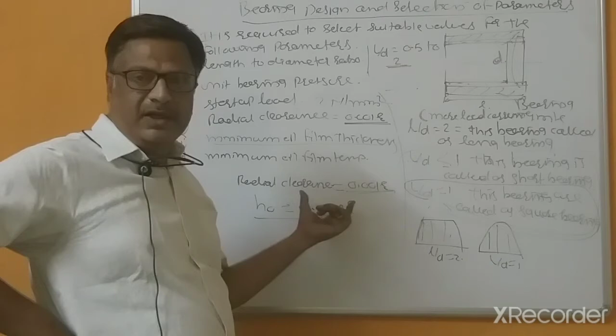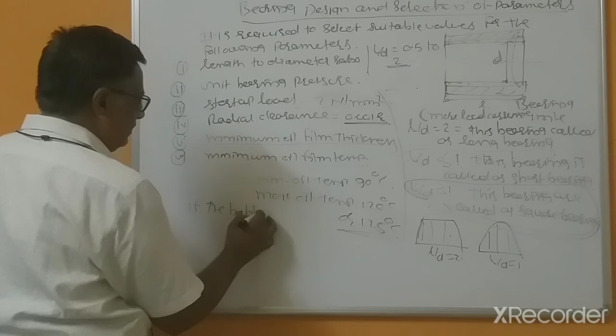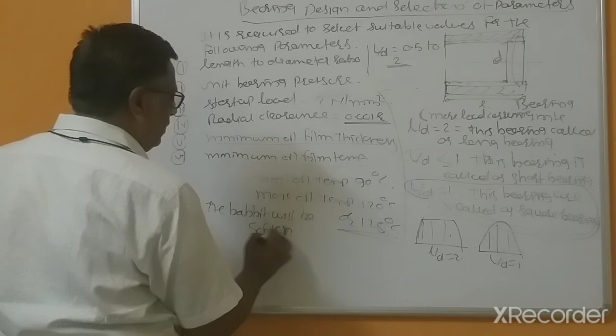And the minimum oil film temperature is up to 90 degrees centigrade and the maximum oil temperature is 120 or 125 degrees centigrade. If it rises above 120 or 125 degrees centigrade, the lubricating oil oxidizes, and the Babbitt material will be softened. Material softening, because of the rise of temperature, means more wear rate. So that's why 90 degrees centigrade is the minimum and 120 degrees centigrade is the maximum oil temperature which is to be allowed.